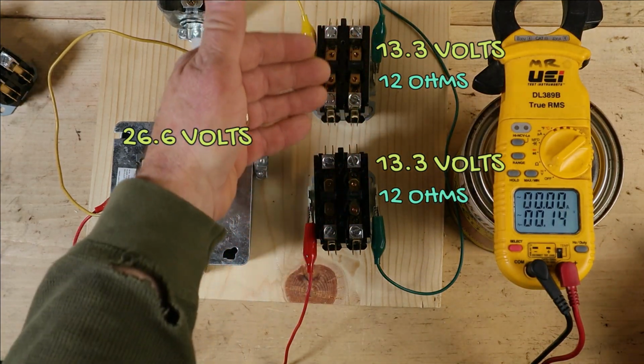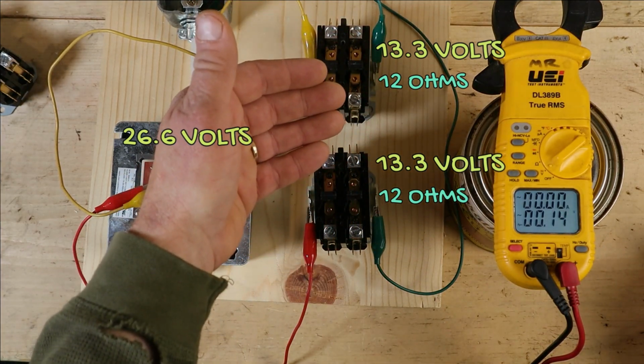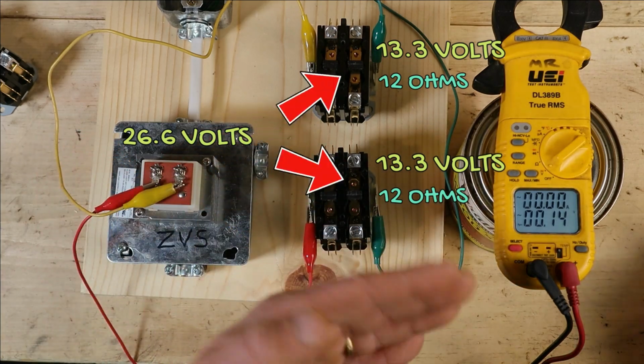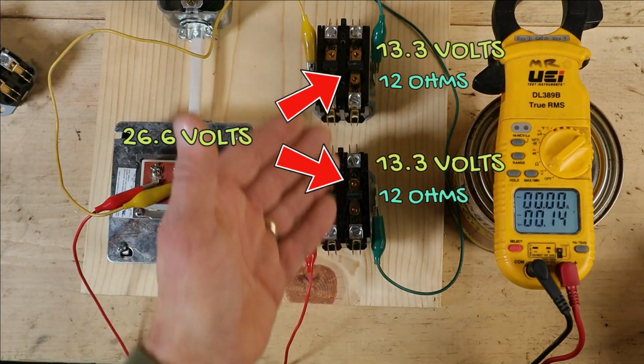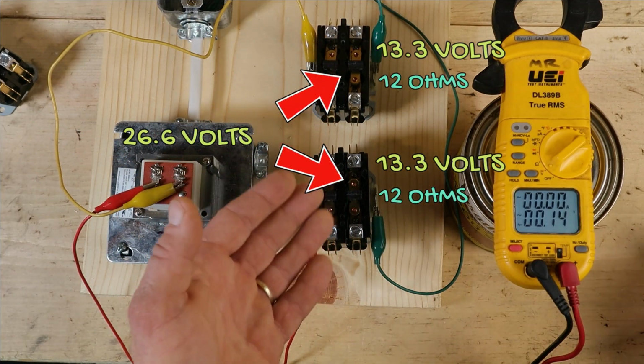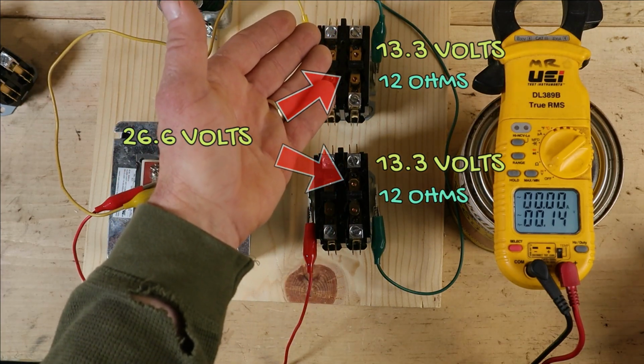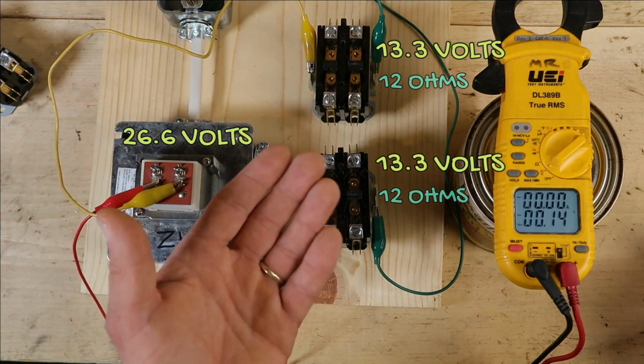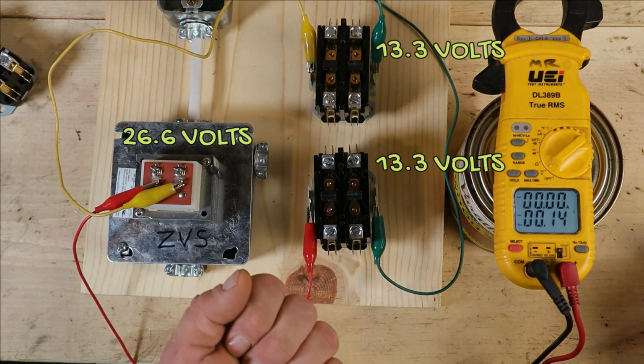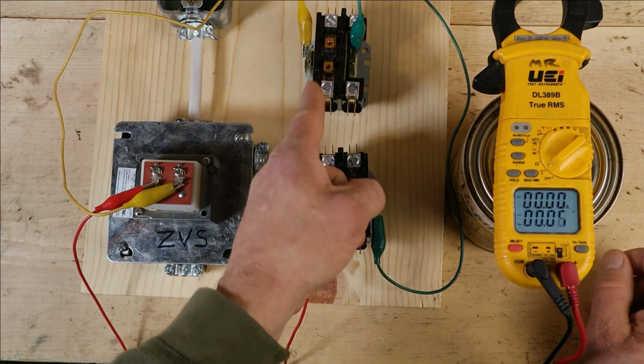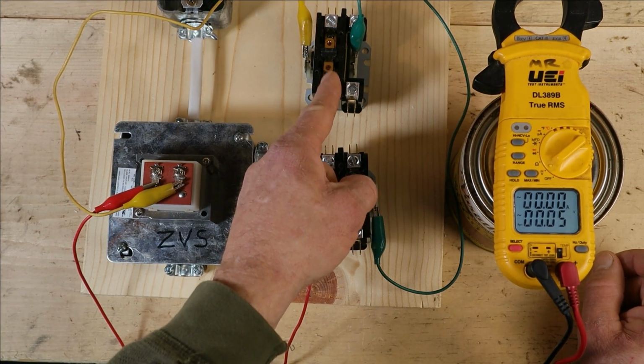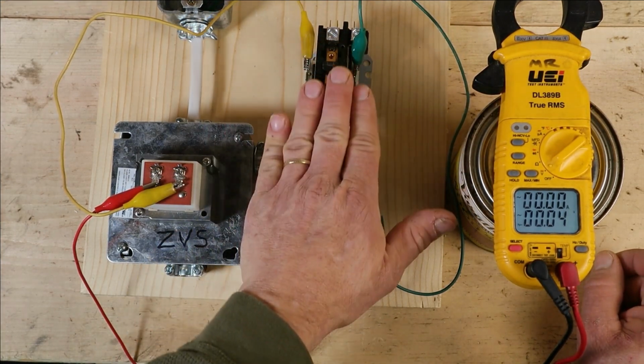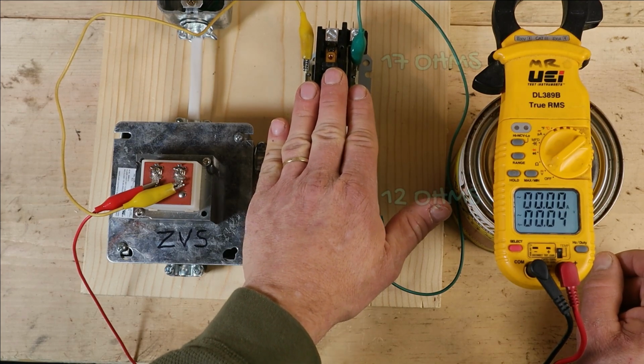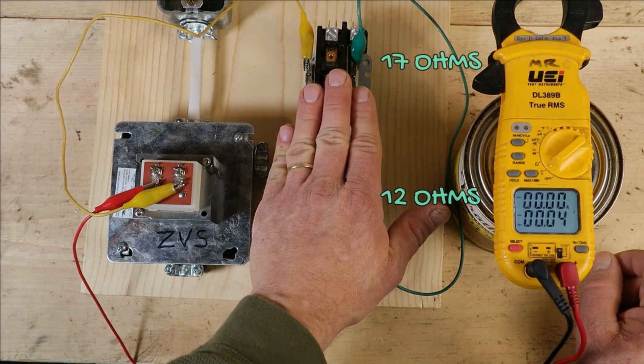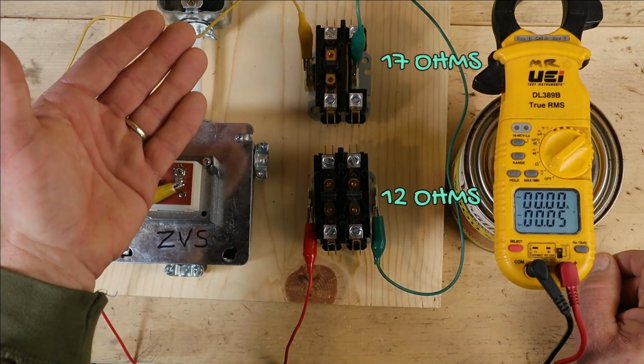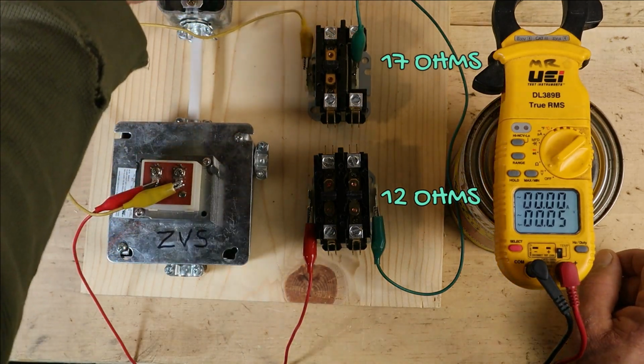Because both of these contactors have the same resistance value, they split the voltage evenly. We have 13.3 volts here and 13.3 here, and neither of those voltages is enough to pull in the contactor. Now I put another contactor in here, a single pole contactor with a slightly higher resistance. This has 17 ohms to it. So let's turn our power on and see what happens.